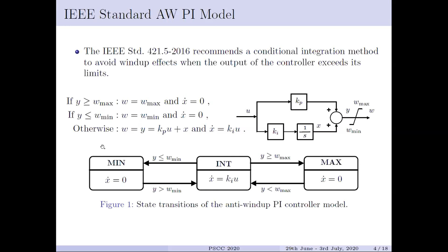The IEEE standard recommends a conditional type anti-wind-up PI controller model to avoid the wind-up effect. The conditional integrator sets the input to the integrator to 0 when the control output is beyond its limit. This figure shows the state transition of the anti-wind-up PI controller model. Observe that this model has three states: the integration state, the maximum state, and the minimum state.